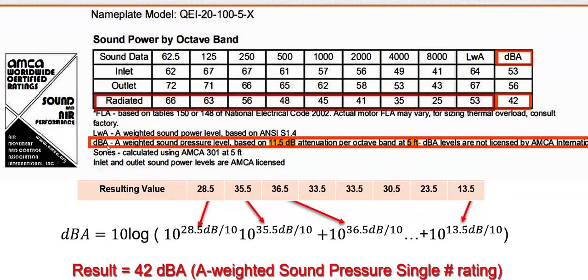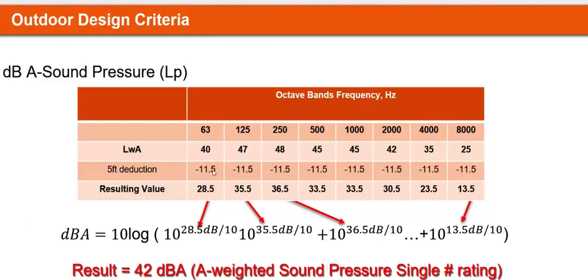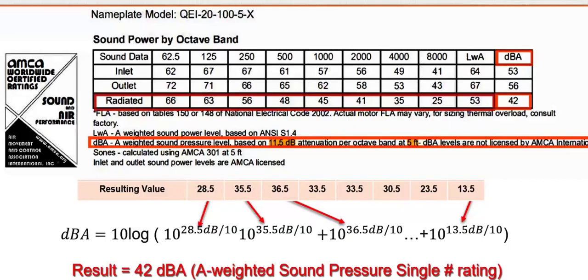Now, when you read the small writing on the cut sheet, it's telling you that it's accounting for almost 12 decibels of reduction on each frequency to mimic 5 feet of distance. When you hear something, you have to be at a distance away to be able to measure that pressure. So looking at that calculation, almost 12 decibels, so 11.5 decibels on each frequency, gets deducted. That gets logarithmically added to get the 42 dBA single number rating, A-weighted. So now you're experts, and anytime you see sound power levels on a piece of equipment on a cut sheet, you're going to know that LW is the sound power quantified in a single number, and the next number is how you, or the occupants, are going to hear it at 5 feet.